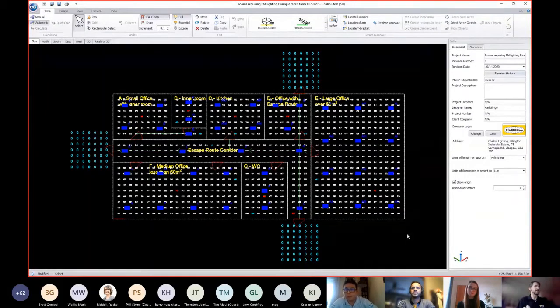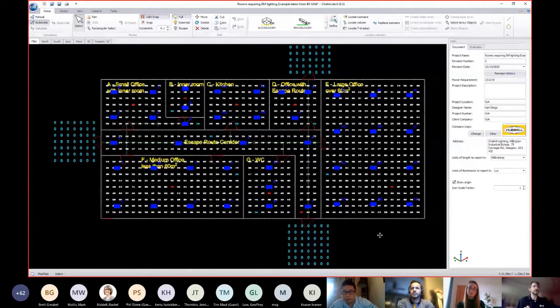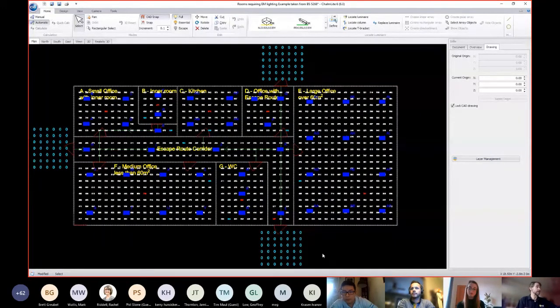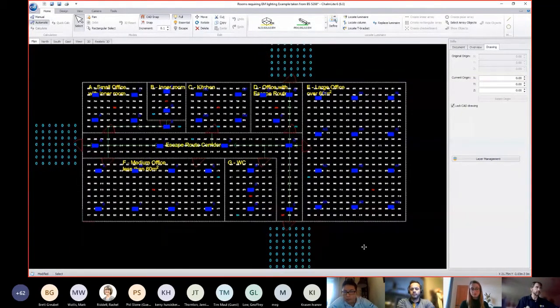This is a layout of a building which is popularly used in the standards to demonstrate where and when you need emergency lighting. Every room here has been populated with lighting fittings. They're all normal fittings, and they're all hitting the levels for offices or toilets or corridors or whatever you're looking at there. I think we've got a kitchen here as well. So what I'm going to do first of all is take you through this example. The first thing I would do here is to turn all the fittings in open areas, i.e. rooms which require the open area lighting, I'm going to light them to half a lux minimum. So I'm going to go through it room by room.